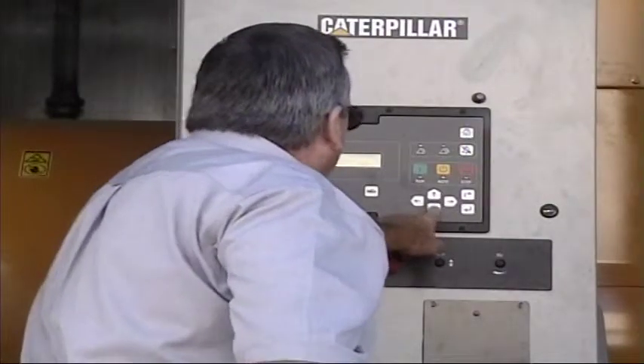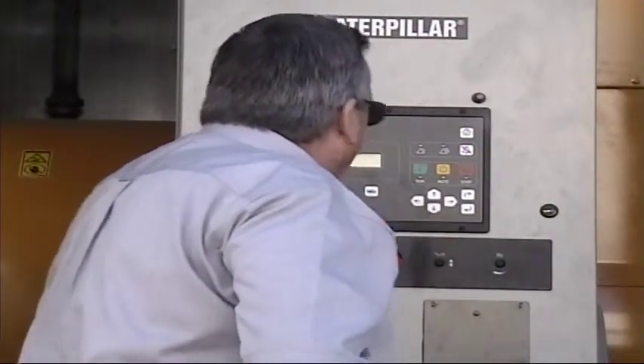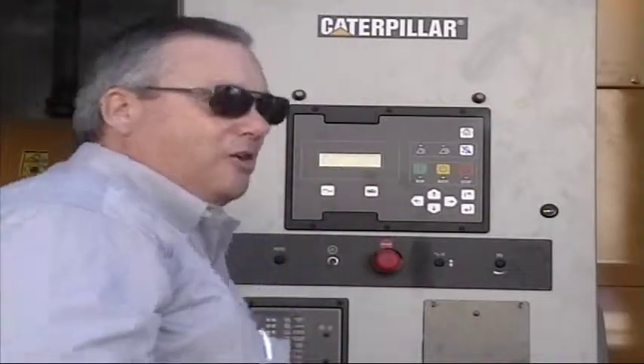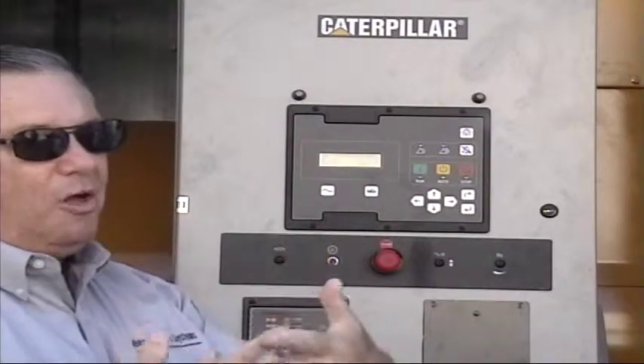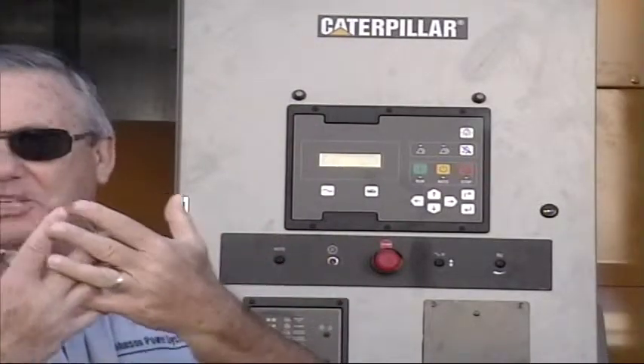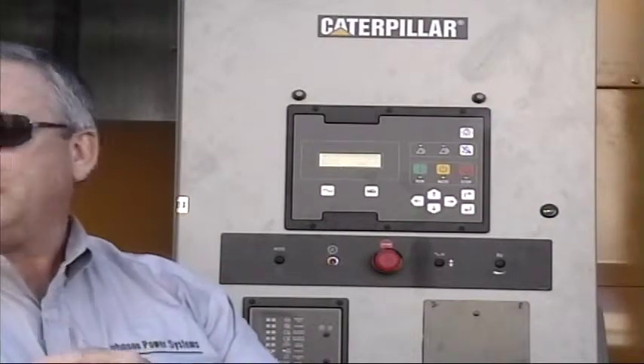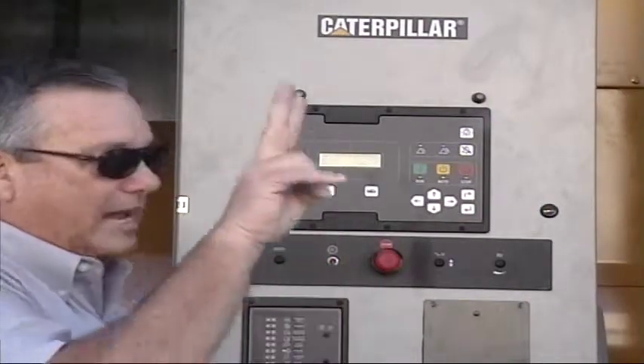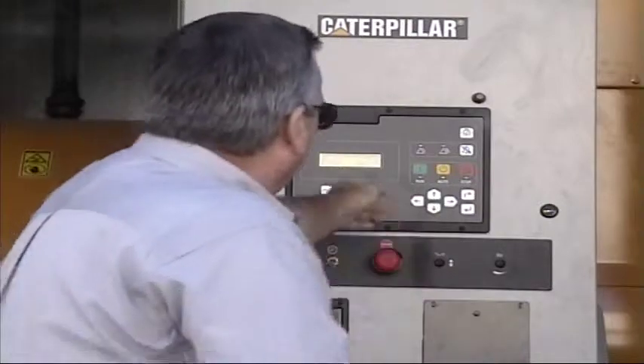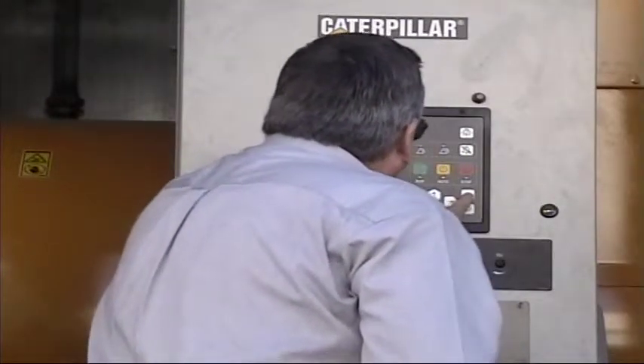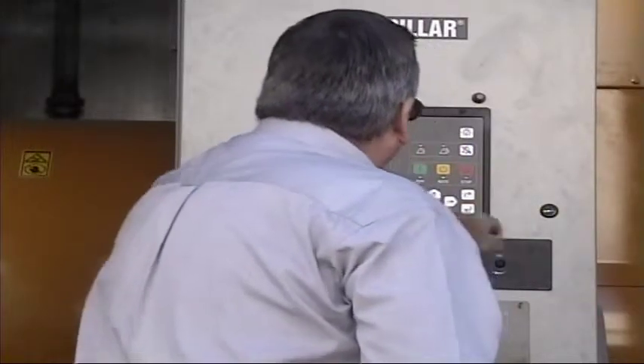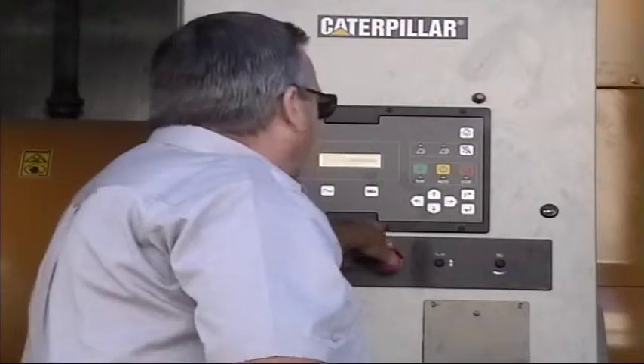And then I push the down key, and then generator breaker open in this case is a fault, or not really a fault, but it shows up as an annunciation — it's an event and it's present. Okay, so we got two things present right now. But what I'm going to do is get back out of here, and go ahead and go through an E-stop, which is the easiest one for me to demonstrate.